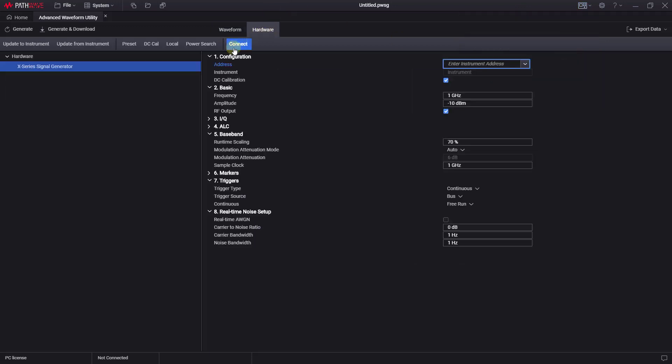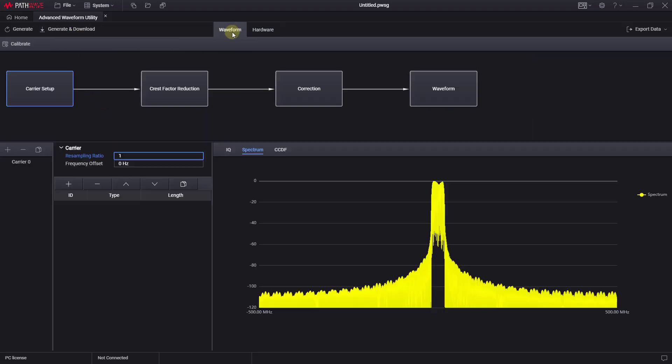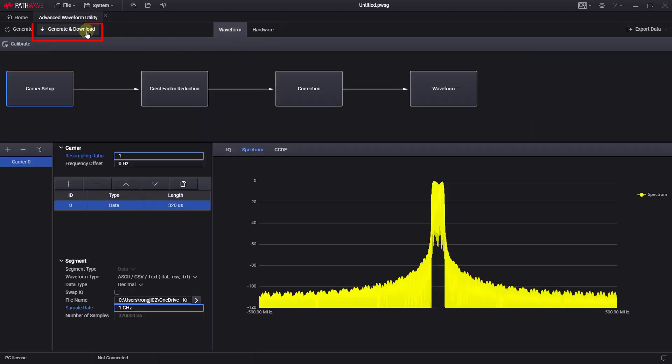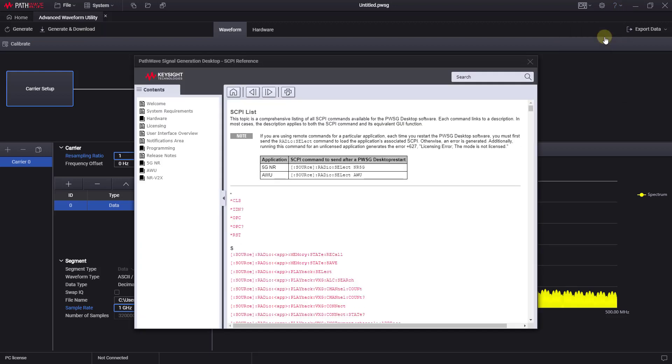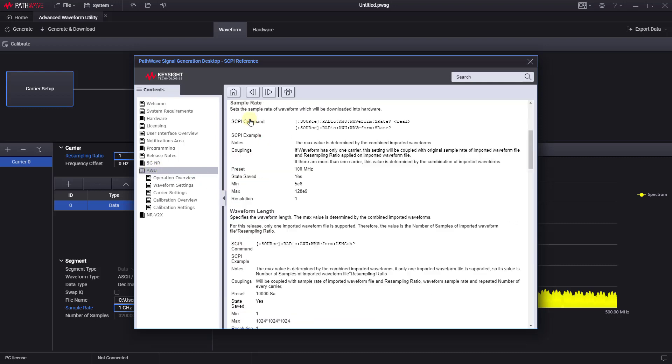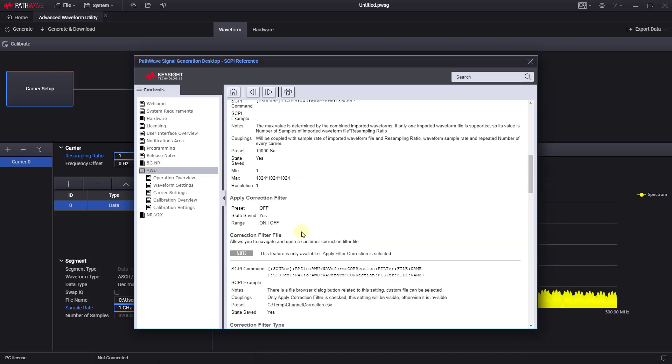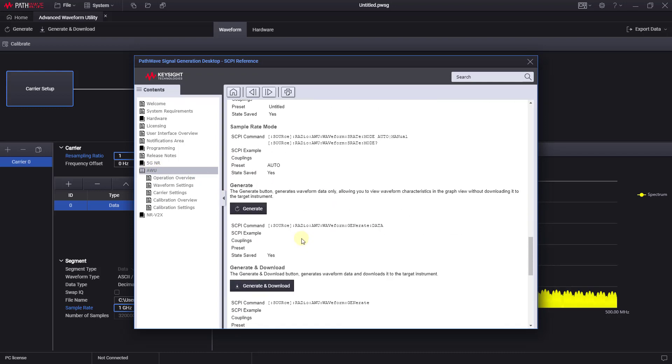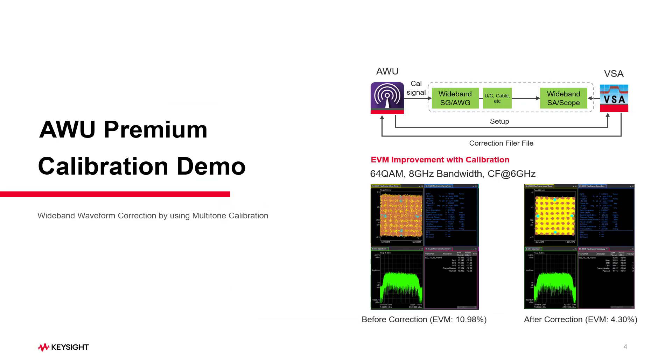which can be configured and connected to. Once configured, simply press generate and download button here to play the waveform on SG. AWU supports remote control through SCPI as well. You can check the SCPI command for each parameter, making it easy to program with Python.